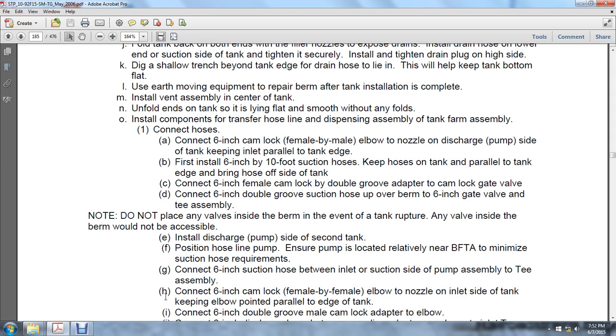Install the discharge pump on the side of the second tank. Position the hose line pump. Ensure the pump is located relatively near to the BFTA to minimize the suction hose requirements. Connect the 6-inch suction hose between the inlet suction side of the pump assembly and the tee assembly. Connect the 6-inch cam lock female elbow to the nozzle on the inlet side of the tank, keeping the elbow pointed parallel to the edge of the tank.